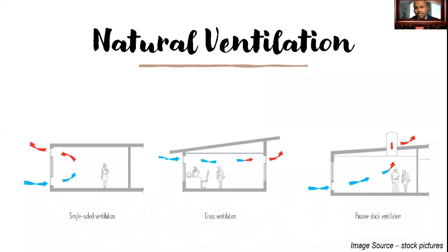Increasing ventilation rate can also be achieved by a combination of methods like natural ventilation. One thing to note here is natural ventilation alone sometimes may not be suitable for some rooms due to their depth, internal heat loads, or other factors. In these cases, some mechanical assistance can be incorporated, like low-powered booster fans in outlets or local comfort cooling devices. So if this is a strategy you are going to pursue, consider using indoor fans in combination with opening doors or windows to further enhance ventilation.